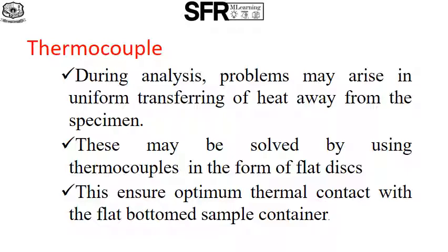Fourth one is the thermocouple. During DTA, problems may arise in uniform transferring of heat away from the specimen. This may be solved by using thermocouples in the form of a flat disk. This flat disk thermocouple ensures optimum thermal contact with the flat bottom sample container. So, a flat bottom sample container and a flat disk thermocouple are needed for optimum thermal contact.